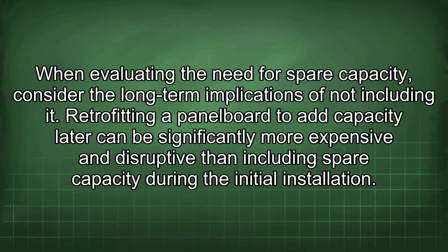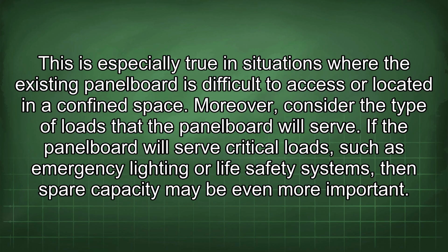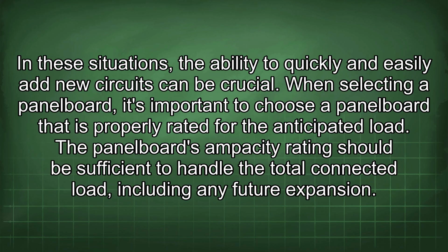When evaluating the need for spare capacity, consider the long-term implications of not including it. Retrofitting a panel board to add capacity later can be significantly more expensive and disruptive than including spare capacity during the initial installation. This is especially true in situations where the existing panel board is difficult to access or located in a confined space. Moreover, consider the type of loads that the panel board will serve. If the panel board will serve critical loads, such as emergency lighting or life safety systems, then spare capacity may be even more important. In these situations, the ability to quickly and easily add new circuits can be crucial.